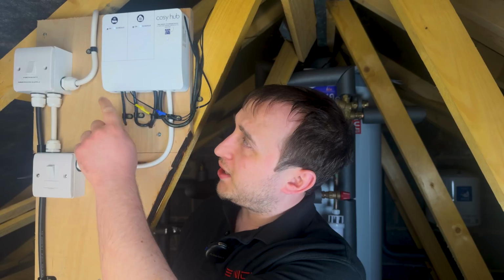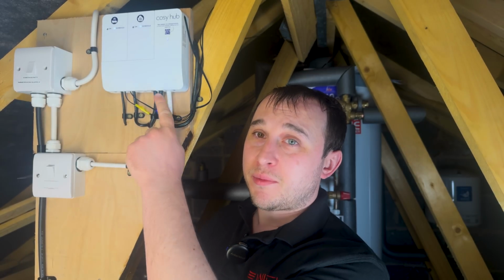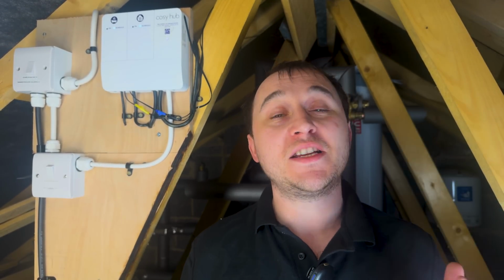Then having a look at some technical information I've got about the Cosy 6 and having a look underneath this cover, I noticed there was an ADC1, 2, 3 and 4, and very quickly realised that ADC1 is a temperature probe coming from here and going into my hot water tank. Next, we had to work out what this temperature probe is, because you could just buy any temperature probe, but that doesn't mean it's going to work.